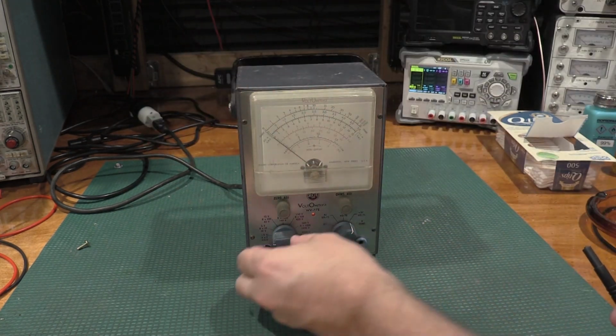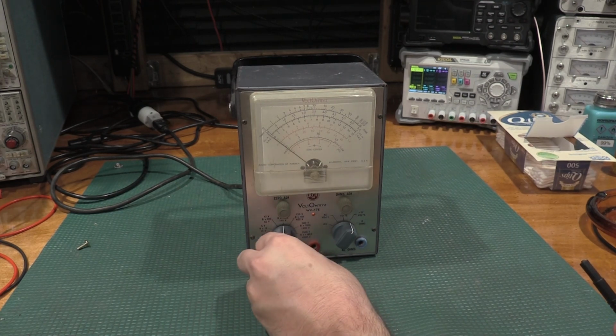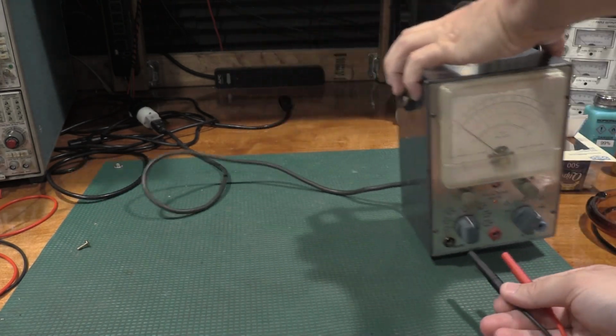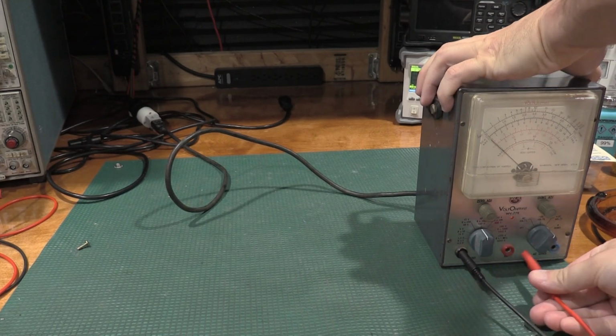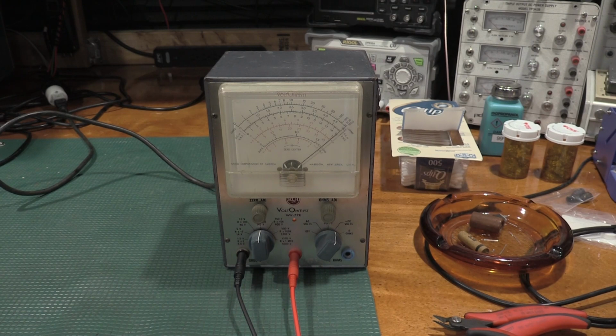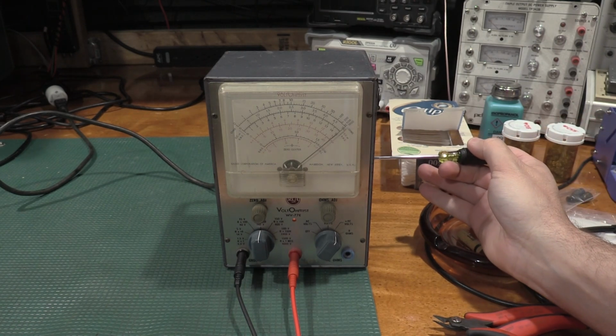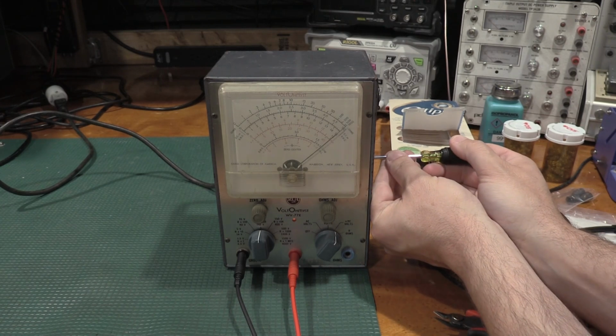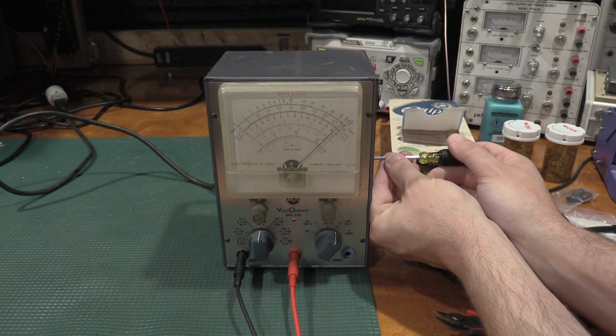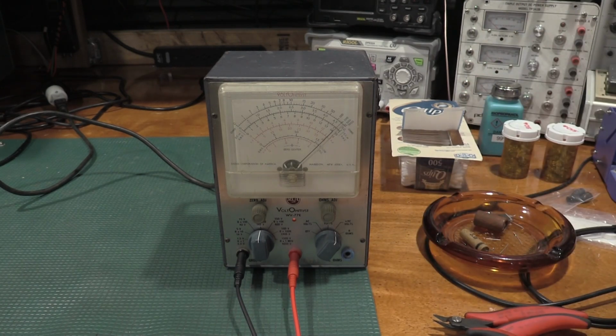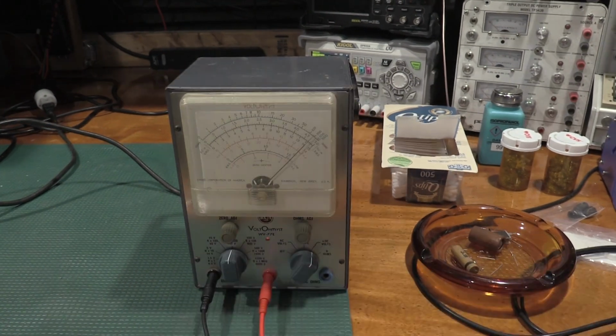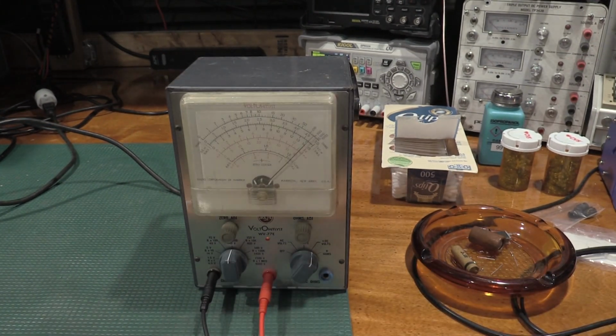So, let's see, we need to be on the 50 volt range. Right there, DC plus. Move this over so my leads reach. And I need to adjust the DC pot for 47 volts. So, we go into DC. And there's 45, 6, and 7. But I have parallax error, so I'm going to move the camera. And there's our 47 volts. Way more accurate than that would ever be in the field.